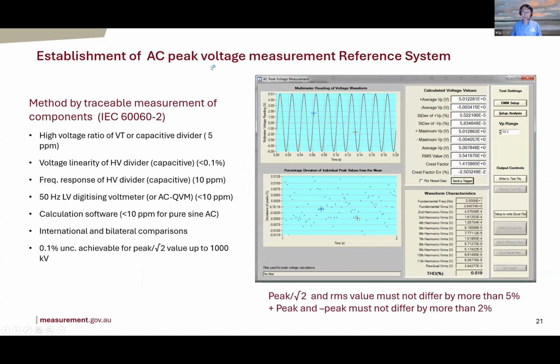And now it's definitely the PD AC peak voltage measurement. So RMS, we know how to do that. It's quite well known. So basically you have digitizers to digitize the waveform, and you first need to determine the ratio of your HV device, either a voltage transformer or capacitor divider. That can be done fairly accurately, and then voltage linearity also, say 0.1, 0.05%, and then frequency response. You need to measure the frequency response of AC dividers because the waveform, the physical component, allows up to 7 harmonics, I think, in the IEC standard. So you need to be able to measure a wide range of AC. That's why you need to measure that.